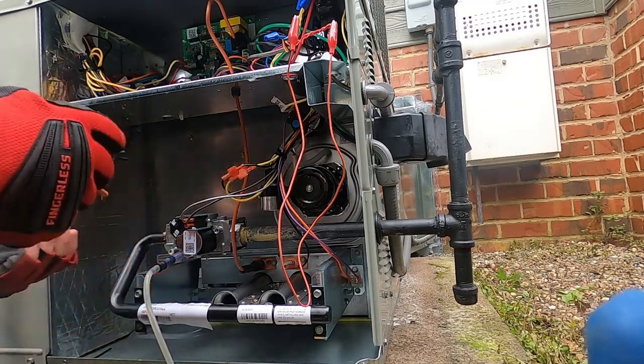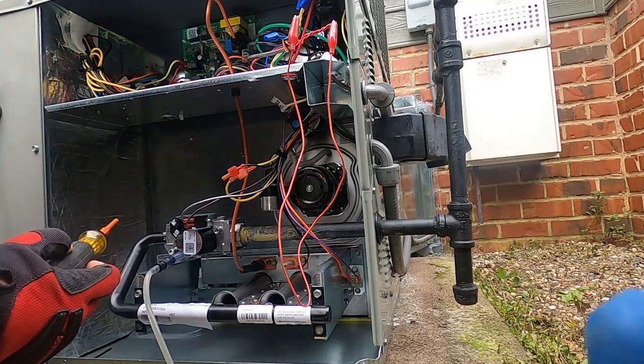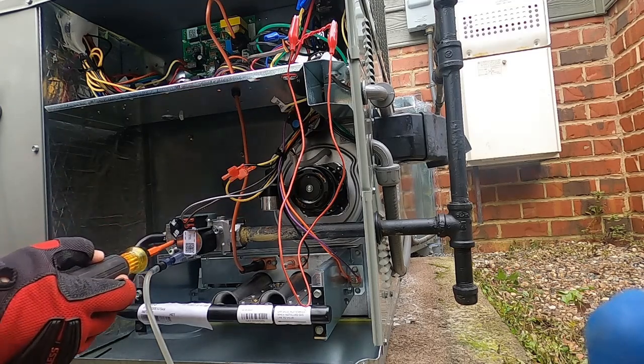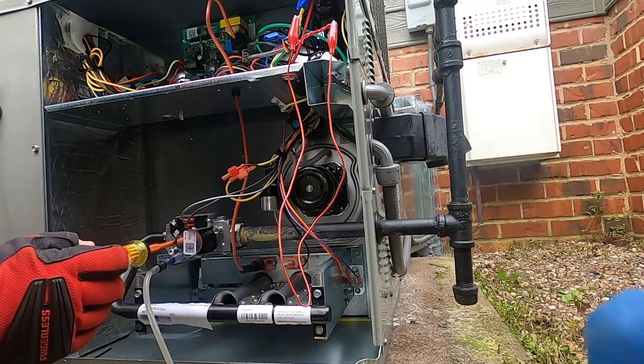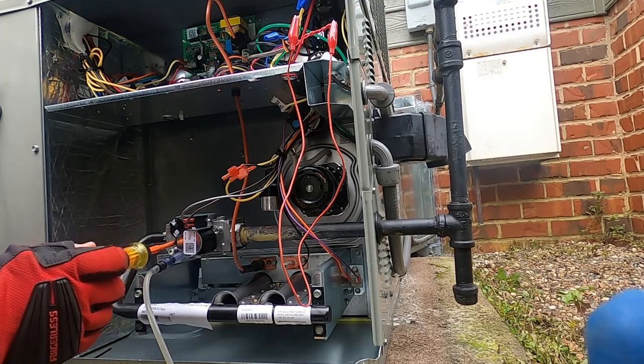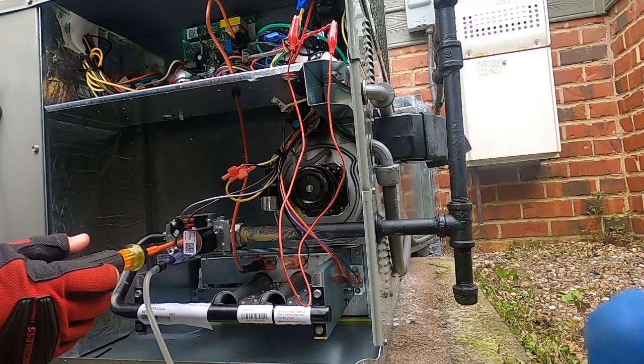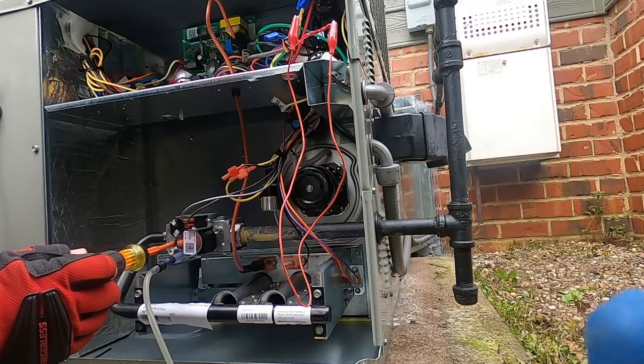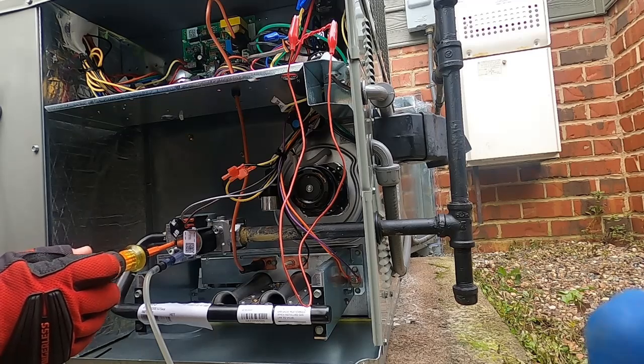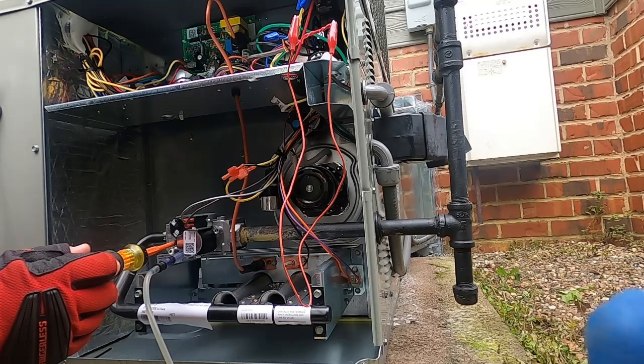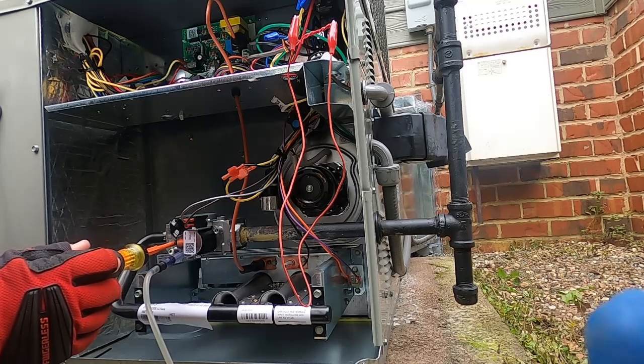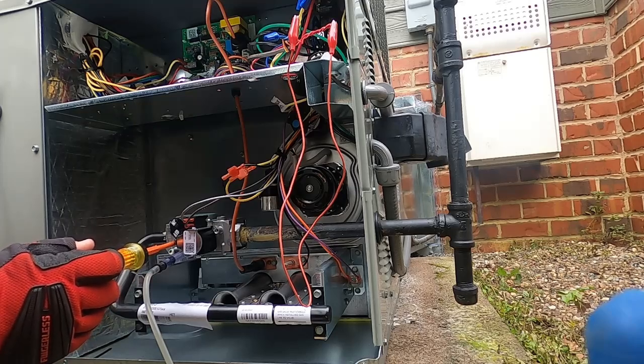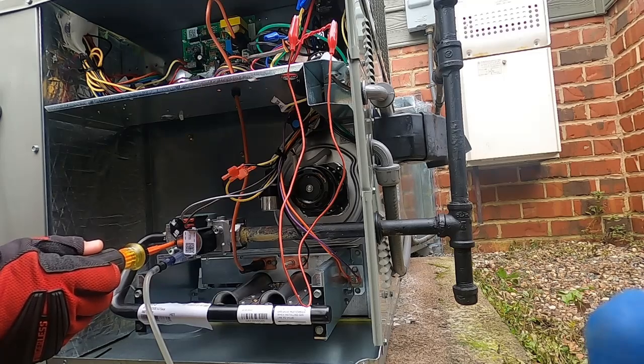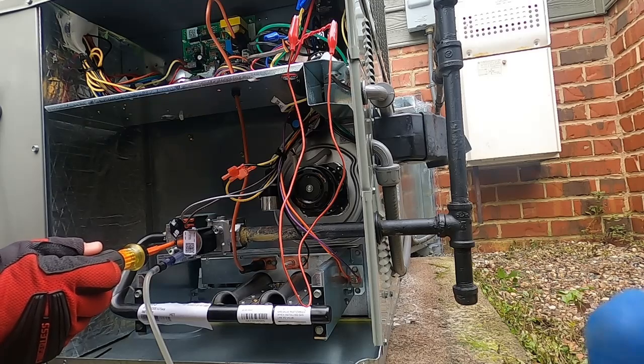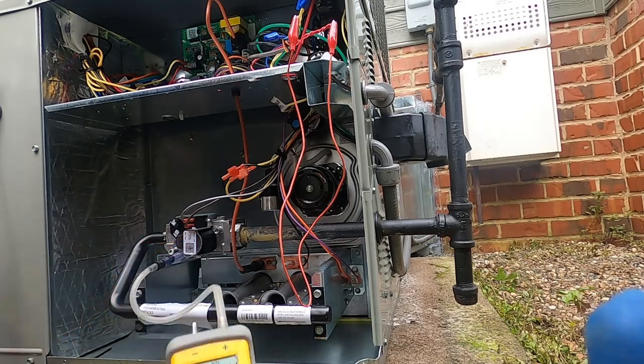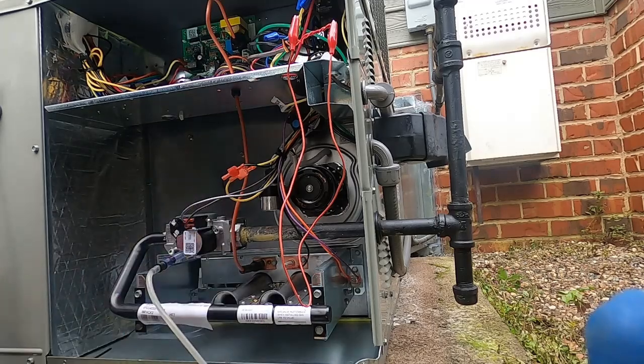With these package units, downstairs system, downstairs heat runs more than your upstairs heat because hot air rises. You're always trying to keep the downstairs warm. You get a real cold night down in the teens, and your gas pressure is supposed to be 3.3, in some cases 3.2, and somebody has it set at 3.5, 3.6, then you get a real long run time back to back to back on a 17, 18 degree night. You start tripping the high limit on these things. So you really want to make sure you're on point with your gas pressure on your downstairs units. So we are now at 3.3. So we are good on our gas pressure.